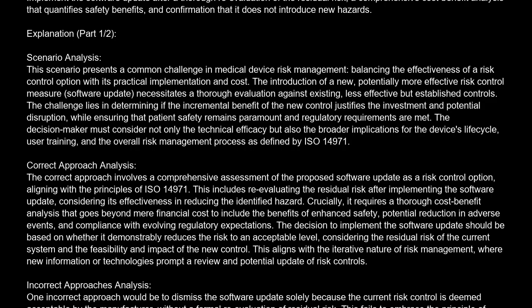The decision-maker must consider not only the technical efficacy, but also the broader implications for the device's lifecycle, user training, and the overall risk management process, as defined by ISO 14971. Correct approach analysis. The correct approach involves a comprehensive assessment of the proposed software update as a risk control option, aligning with the principles of ISO 14971. This includes re-evaluating the residual risk after implementing the software update, considering its effectiveness in reducing the identified hazard.